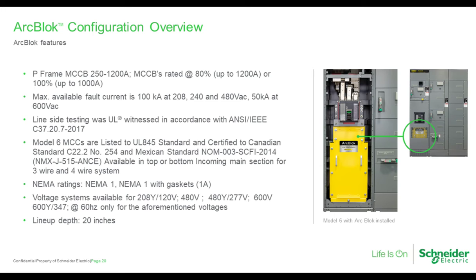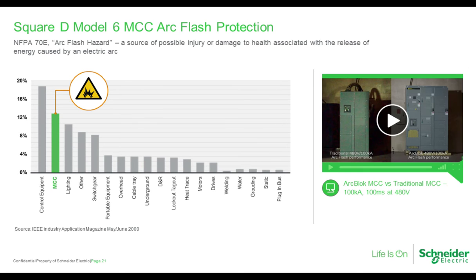Here are the technical features of the Square D Model 6 MCC available now. It's up to 1200 amp and will be expanded to higher amperages in 2020. It's available for up to 100 kA withstand current at 480 volt. It is tested per NEMA and IEEE standards and UL witnessed. It has the standard footprint. In other words, this ArcBlok edition will keep the same small footprint as the standard Square D Model 6 MCC.